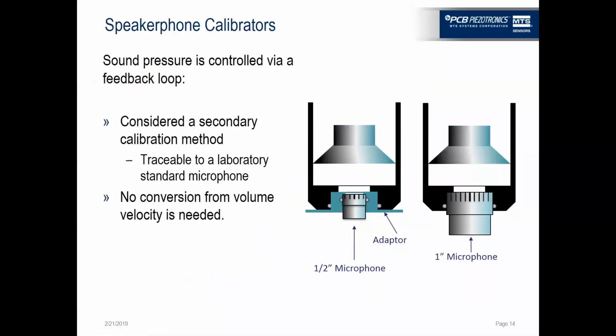On the other hand, a basic speakerphone calibrator tends to be controlled with a feedback loop. Several systems out there simply have large enough volumes that they are not sensitive to any change in volume. Most times, this is considered a secondary calibration, traceable to a laboratory standard microphone. However, a sound speakerphone calibrator has a known sound pressure. You don't have to do any conversions with it after you're done doing your measurements. You know what the sound pressure is. I don't have to tell you what the ambient pressure or temperature of the environment was in order for you to complete your calibration.